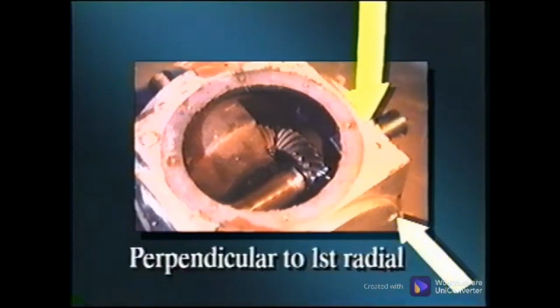These multiple reduction and angle gearboxes may require 2 radial measurement locations to be made at each bearing location, as well as the axial measurement. This second radial measurement should be perpendicular to the first measurement and can provide valuable information that may not show up in the other point.